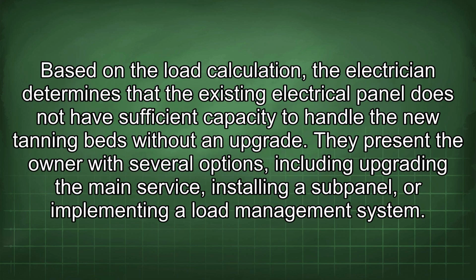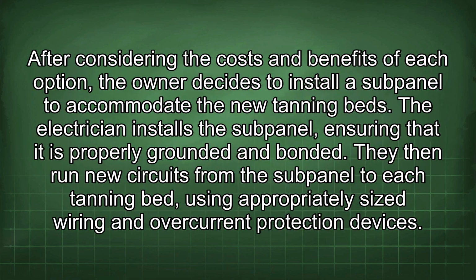Based on the load calculation, the electrician determines that the existing electrical panel does not have sufficient capacity to handle the new tanning beds without an upgrade. They present the owner with several options, including upgrading the main service, installing a subpanel, or implementing a load management system. After considering the costs and benefits of each option, the owner decides to install a subpanel to accommodate the new tanning beds. The electrician installs the subpanel, ensuring that it is properly grounded and bonded.